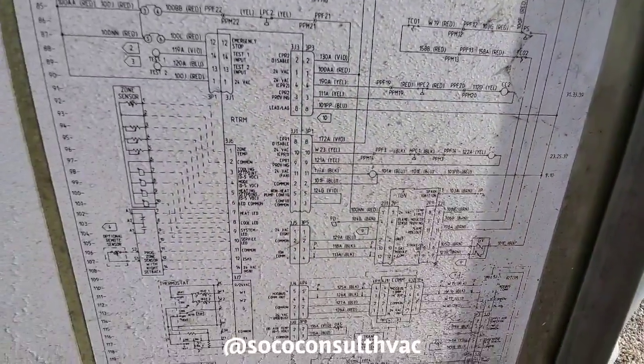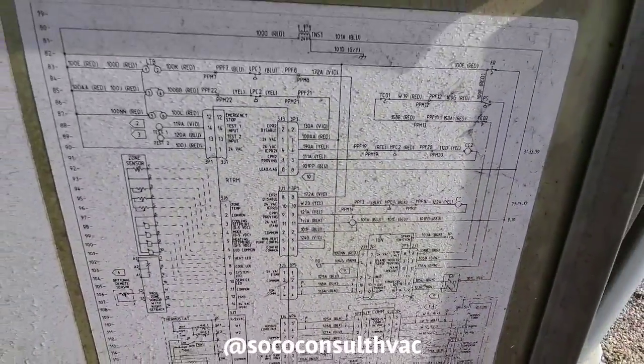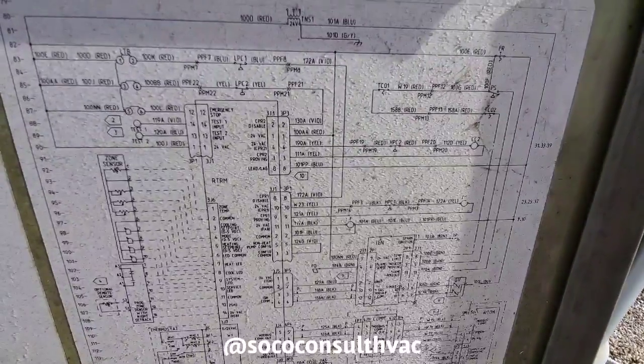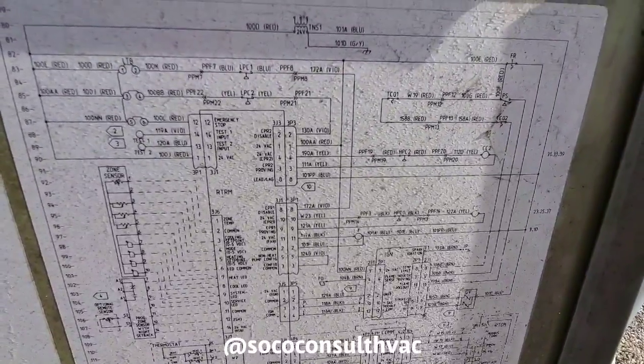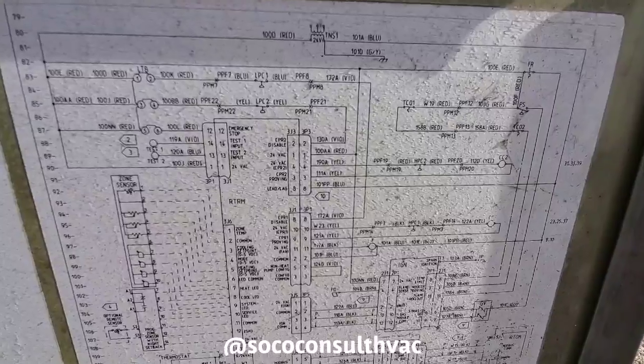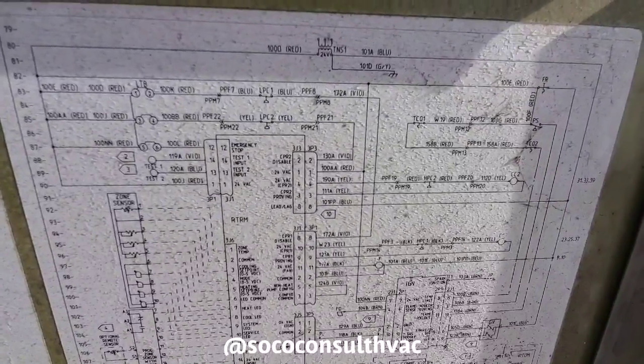And I'm going to tell you, more likely than not, it is contactors and relays that cause low voltage shorts besides skinned wires. So now we're going to isolate the contactor, pull the wire off of it, and see if we still blow a fuse.